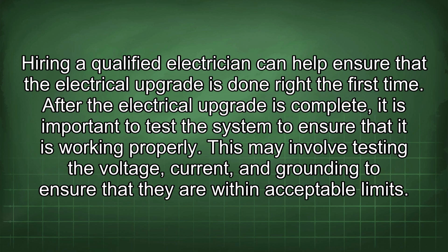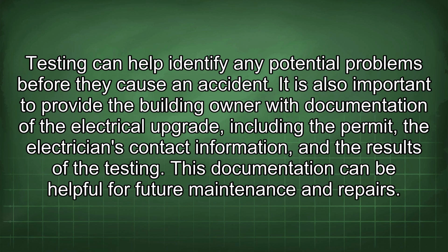After the electrical upgrade is complete, it is important to test the system to ensure that it is working properly. This may involve testing the voltage, current, and grounding to ensure that they are within acceptable limits. Testing can help identify any potential problems before they cause an accident. It is also important to provide the building owner with documentation of the electrical upgrade, including the permit, the electrician's contact information, and the results of the testing. This documentation can be helpful for future maintenance and repairs.